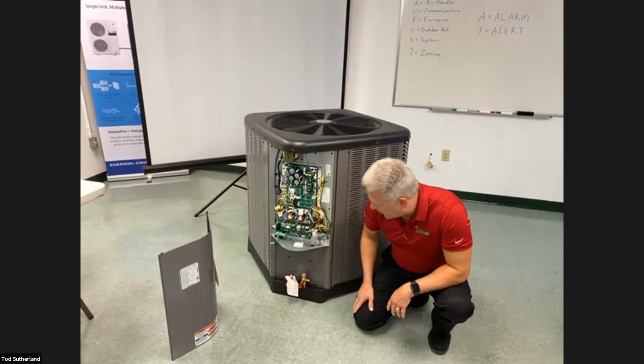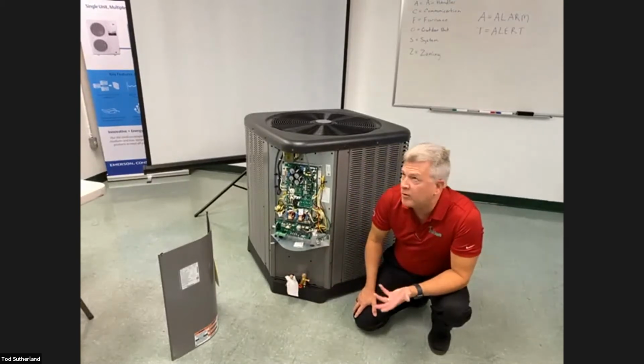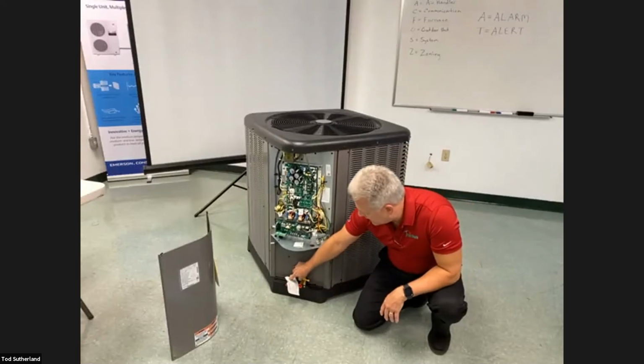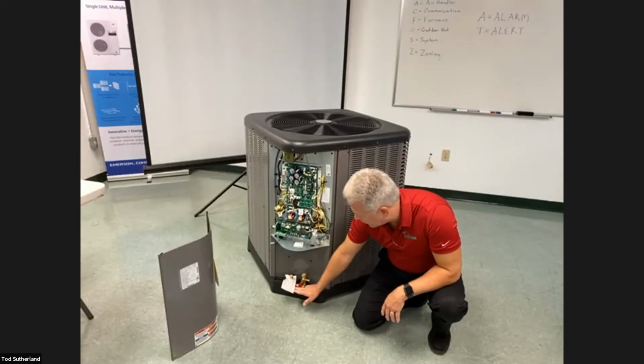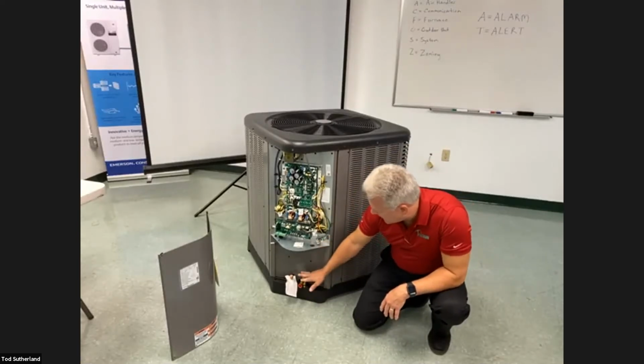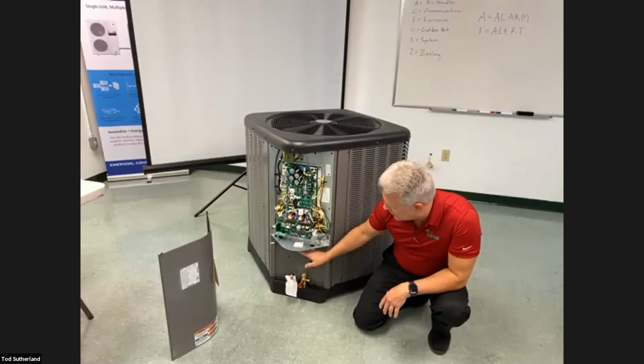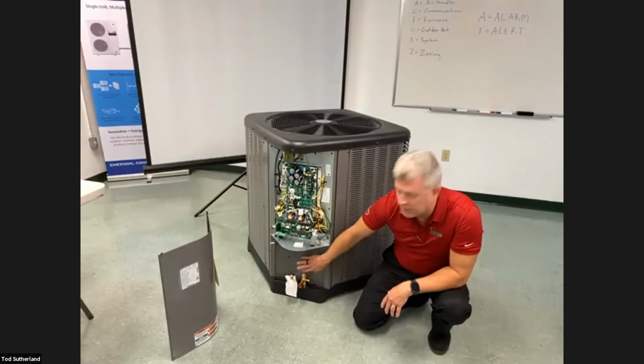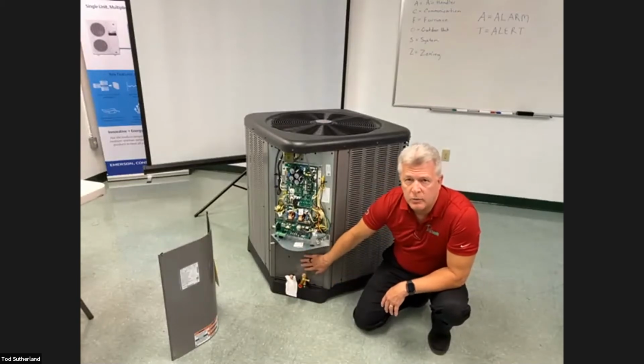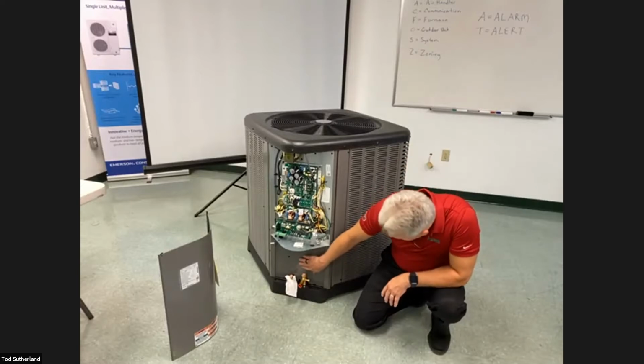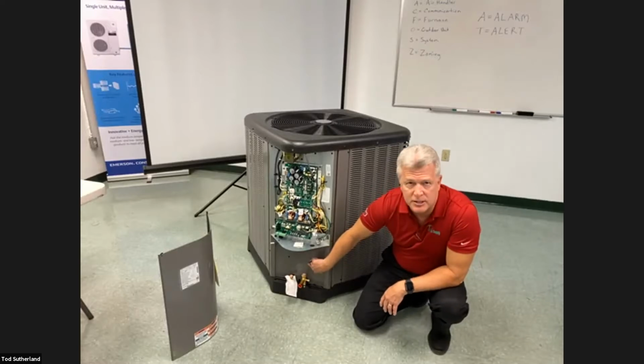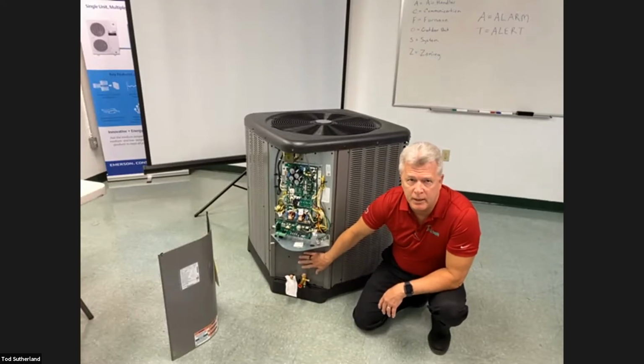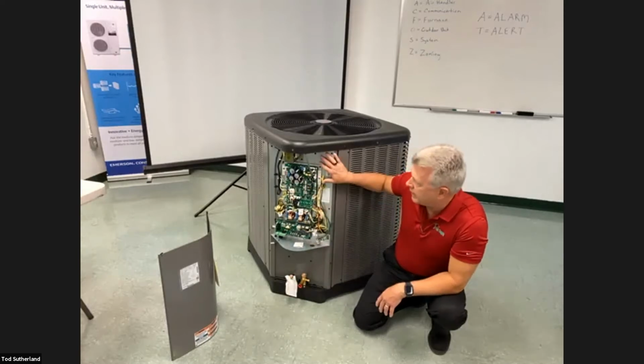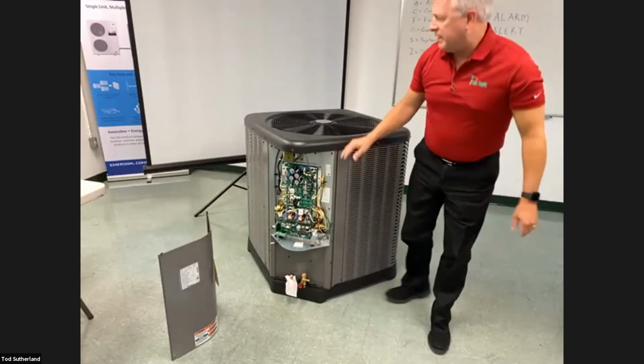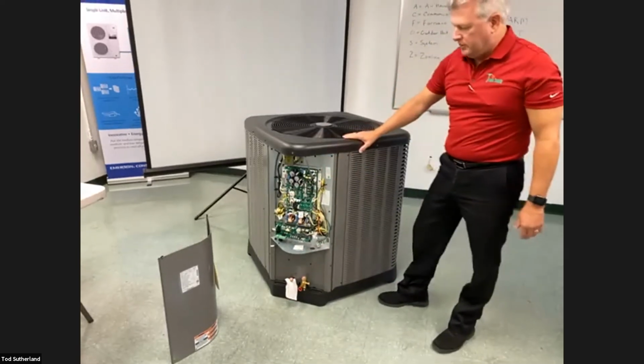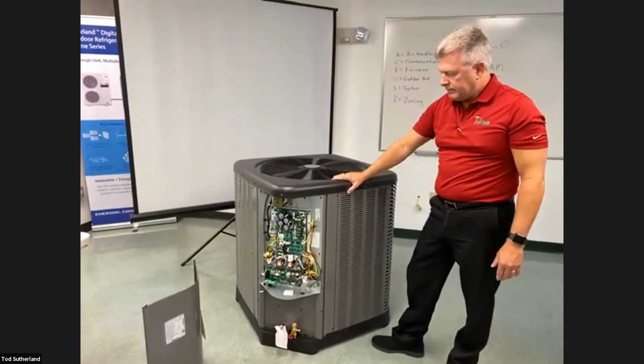You have what they call their 3, 4, 5 valve, where basically 3 inches between the valves, 4 inches from the ground up to the valves, and at least 5 to 6 inches here above the valves. You also have an access window here. With this access window, you can remove 2 screws and you're able to put your test instruments up inside the unit and run the unit without having this big panel removed. Okay, those are all features that are common to all the Ruud units.